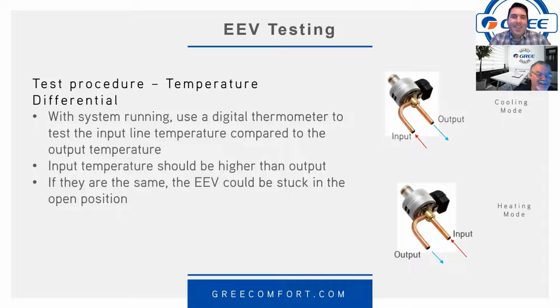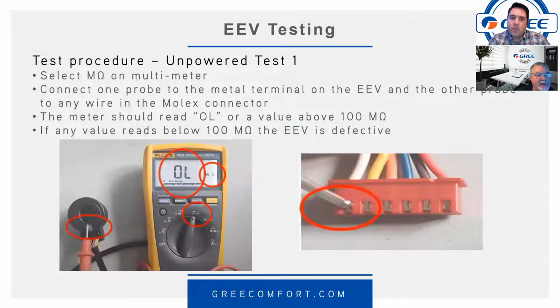Thank you. So test procedures, temperature differential on the EEV. When the system is running, use a digital thermometer to test the input line compared to the output. It should be higher on the input than the output. If they're the same, the EEV could be stuck in the open position. A couple of things that you might be able to do to resolve that issue, we're going to cover in our tips and tricks. Then other testing procedures. And this is all going to be out there, and again, is going to be in our service manual.